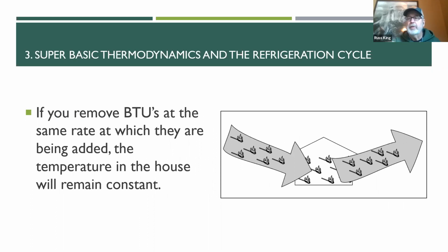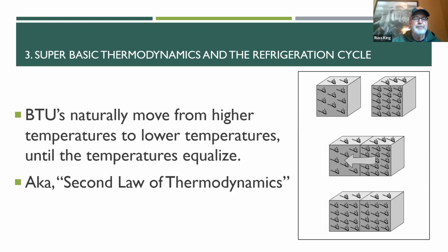So in a house, the BTUs are naturally leaving at a certain rate and we're adding them back in at the same rate to maintain a constant temperature. By the way, that rate changes because the outdoor temperature changes. So your equipment has to have the ability to cycle on and off, otherwise it just keeps adding and adding and adding, and then if it's not as cold outside, you start overheating inside the house. So it's this fine balance that we have to maintain in order to keep a constant temperature inside the house.